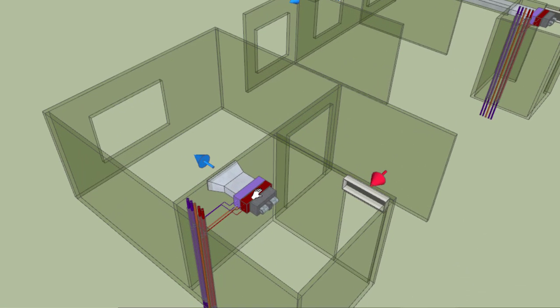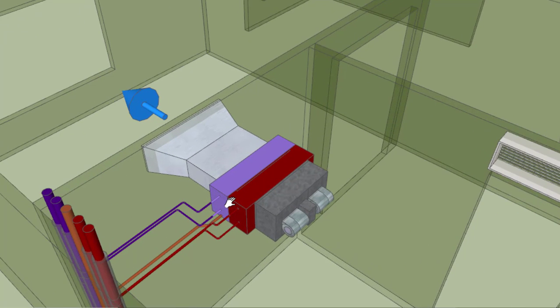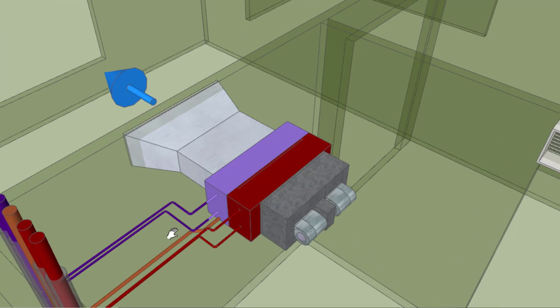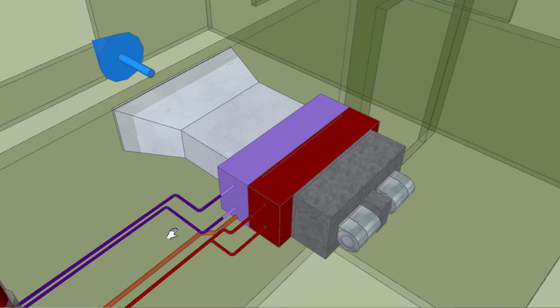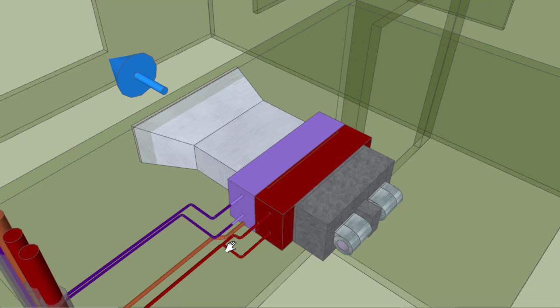First of all we have a concealed type FCU which is taking this return air and conditioning this air and supplying it to the same zone. Here as you can see we have four pipes. This is a four pipe system in which two pipes are used to take the chilled water to the cooling coil and the other two pipes are being used to take the hot water to the hot coil. These are two fans inside the FCU.